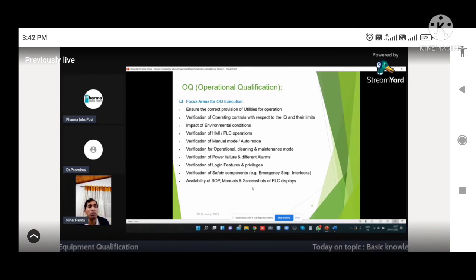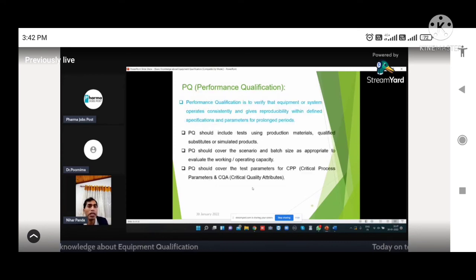Then verification of safety components like interlocks and emergency stop, whether those are working or not working, and what the ranges are; we need to verify those things also. Availability of SOP, manual, screenshots of PLC displays. You should keep the SOP ready, at least the draft SOP during the OQ part, and other screenshots of PLC. Whatever activities you are doing during the OQ part, you should take proof with screenshots. If you capture the time and date also, that will be better for you, to explain to the auditors that this actually happened, not fabricated documents.